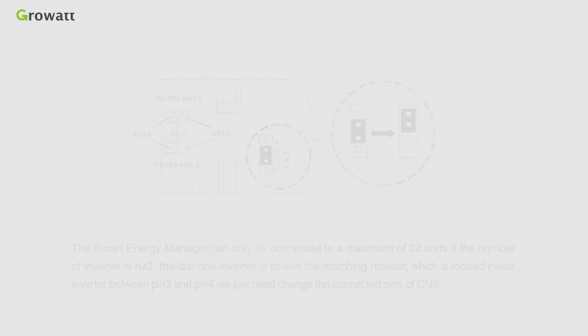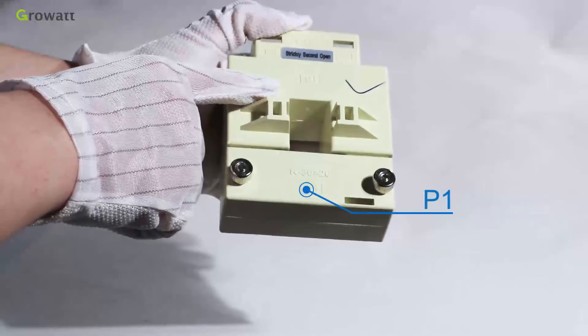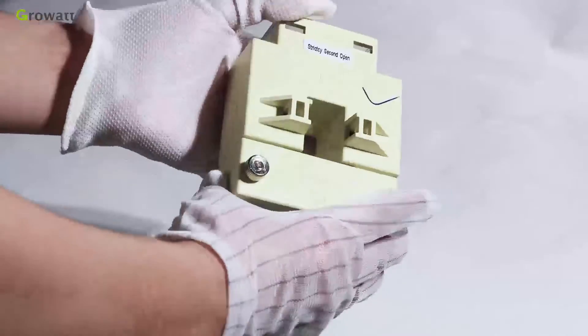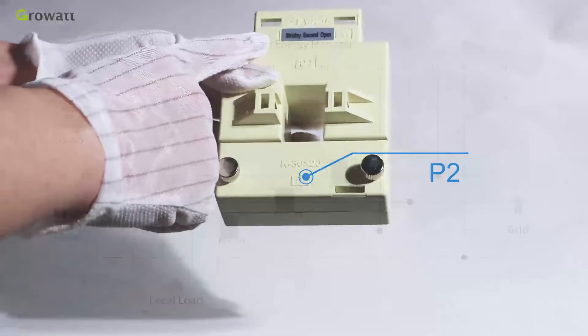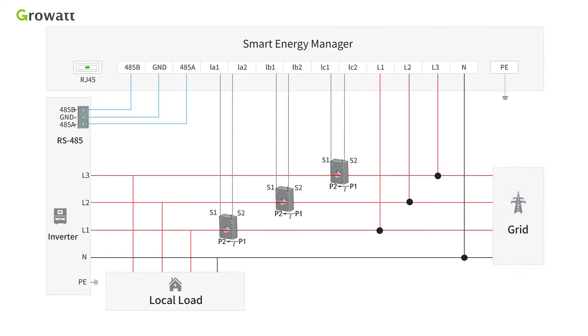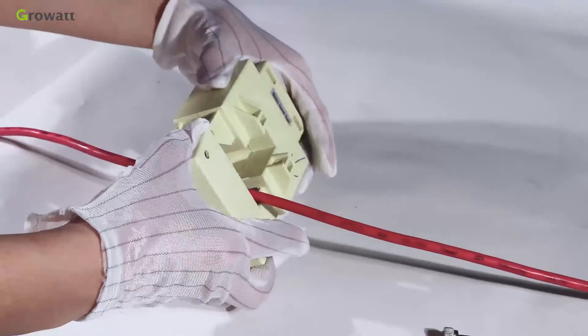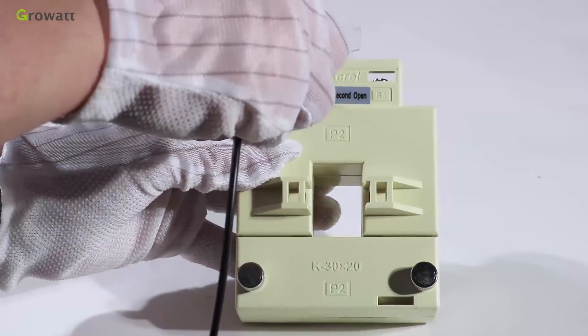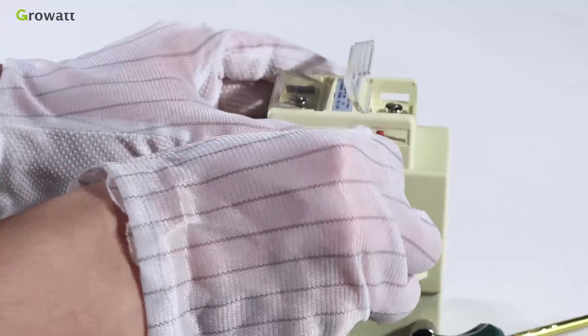CT is the abbreviation for current transformer, which is used to measure the live wire current passing through it. There are P1 and P2 silk screens on both sides of the current transformer to distinguish the direction. P1 side is close to the grid and P2 is close to the inverter and loads. The fire wire passes across the CT's hole, then S1 of CT1 is connected to ia1 and S2 is connected to ia2.